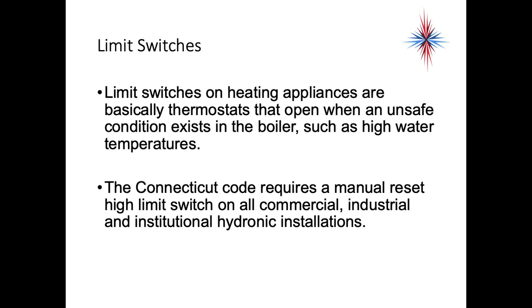Limit switches on heating appliances are basically thermostats that open when an unsafe condition exists in the boiler, such as high water temperatures. We do not ever want water to boil in a boiler unless it's a steam system, so we always have to make sure that the boiler water temperature is under 212 degrees Fahrenheit.